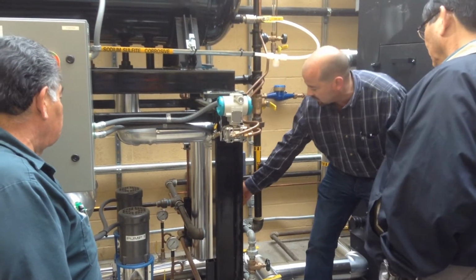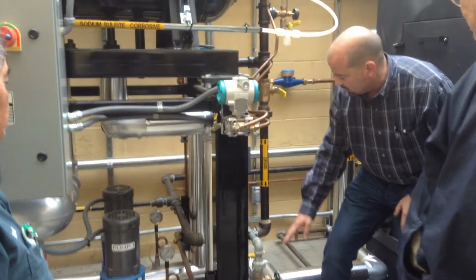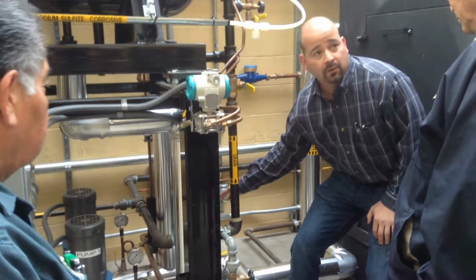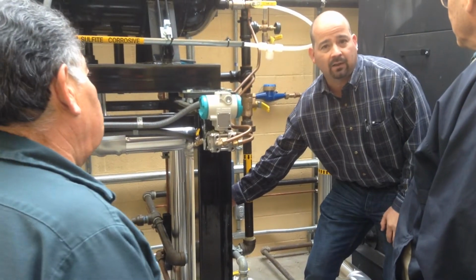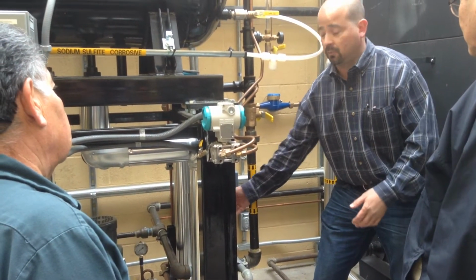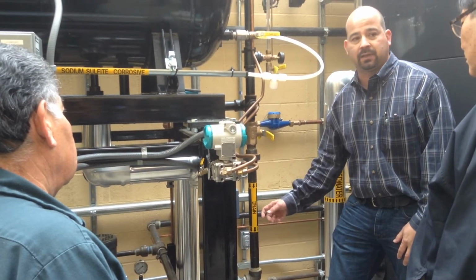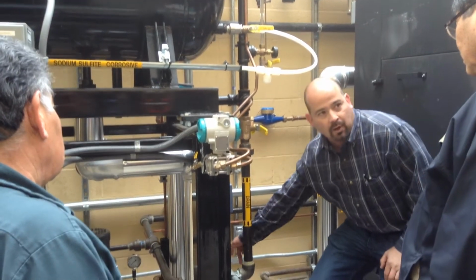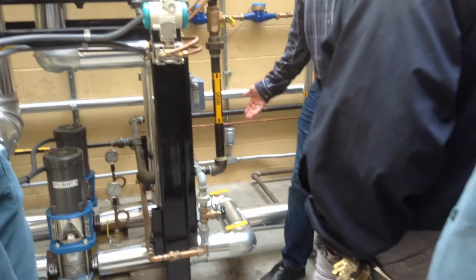And it goes into a modulated feed valve. And you have a bypass around it. The only reason for the bypass around this valve is if something were to go wrong with this valve and you needed to manually keep the system online, you can just throttle this globe valve down here just to get it by until you fix the problem.